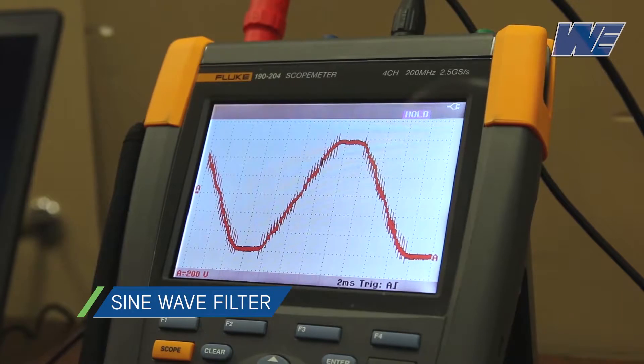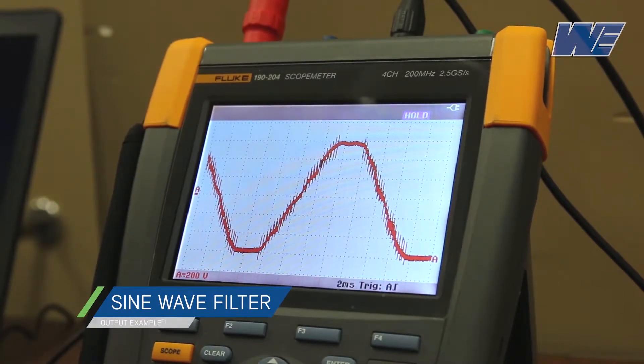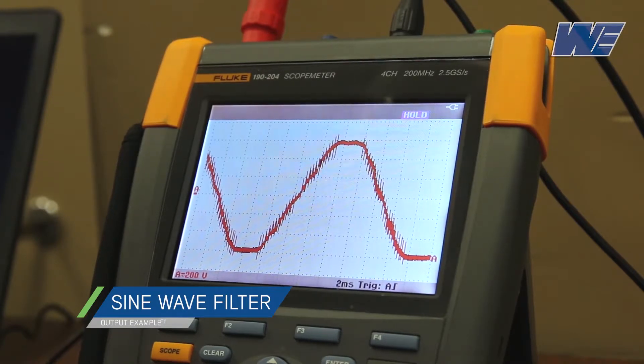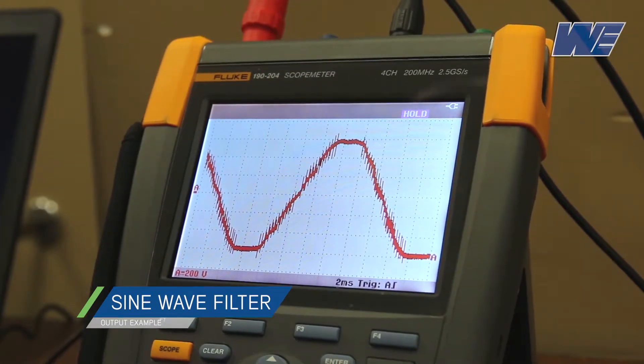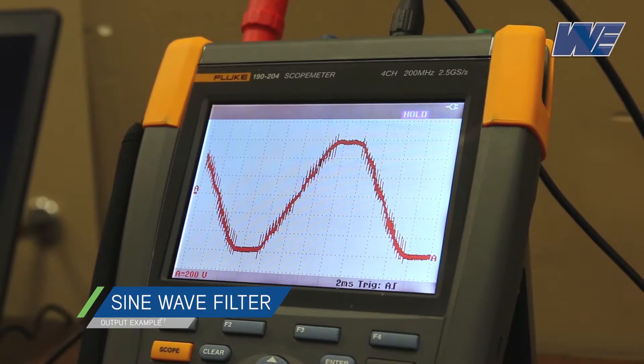Okay, now we've inserted the sine wave output filter between the drive and the motor. Again, there's 500 feet of cable between the drive and the motor. We are on 2 milliseconds per division.